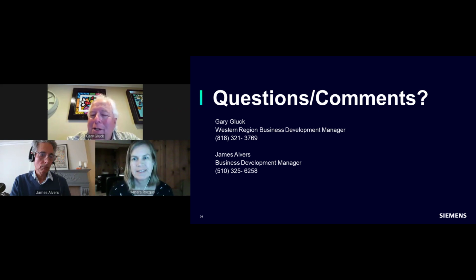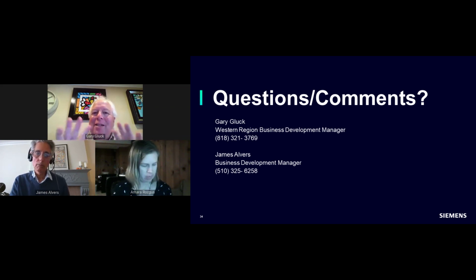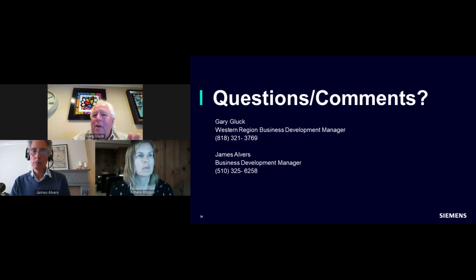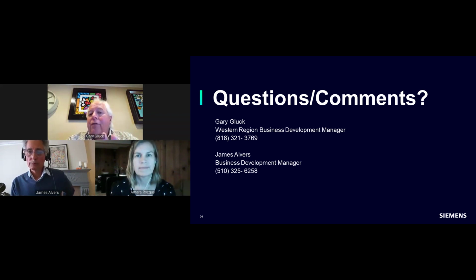Sure, Amara. I saw that question, and I was hoping I'd have the opportunity to answer it. I'm not sure that there's been a steady state that has developed as far as the labeling of these electronic trip units. What I've seen is LSI, we all know, long time, short time, instantaneous. We'll put a G at the end if it's ground fault protection and trip. We'll put an A at the end if it's alarm. And I think what the author of the question was concerned about is, where do you put the arc flash? I've seen it put ahead of the L. So if you're looking for arc flash mitigation and you want the ground fault alarm, that would be ALSIA. When I see that, then I understand it. So there's a little bit of confusion with the two A's and what they mean.